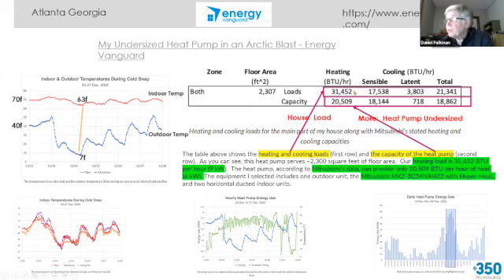The heat pump installed for this house, if you look at the title of the article, was purposely undersized. He purposely installed a heat pump that was under capacity, could not perform at the full load of the house, which tells me he's got a very energy efficient home. The heat pump can deliver 20,500 BTU when the house needs 31,000, unless it's very well insulated.